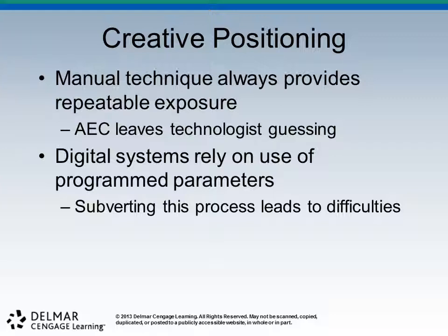And that's when I told you that one kind of gets under my skin when I see people do that. Every time you phototime a patient and you look at that image, you need to know what that mAs was. And it may show up for 10 seconds and then go away. But you need to know what that mAs was. Because if it's not a good image, then you can repeat it the second time and not phototime it the second time, and you'll know exactly what to do. You with me? Well, I'm going to assume that you are. Alrighty.